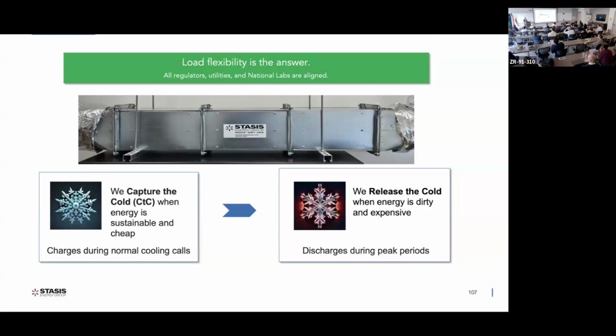So we have 50 to 55-degree air coming off the coil during normal daily delivery of a cooling call. In the process, without any special controls, intervention, or manipulation of the system, we are essentially storing energy during the day.